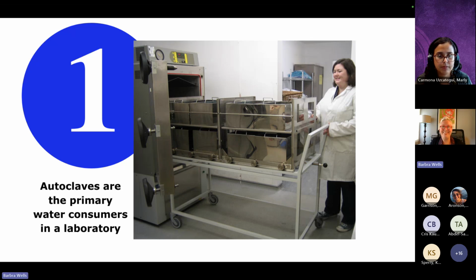Why do they use so much water? Autoclaves use water for three things. First, to generate steam, obviously. Second, they use water for effluent cooling. When a typical autoclave is in use or idle, steam is condensing inside it, and that condensate must be cooled before it can drain.